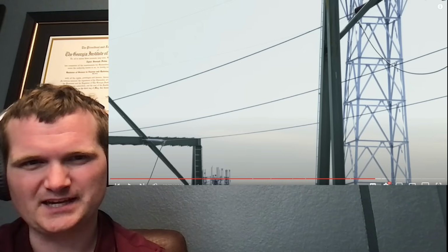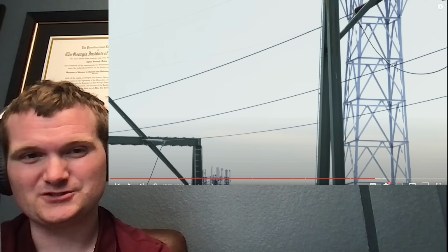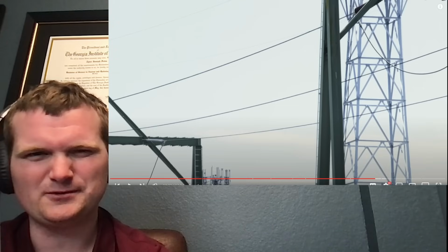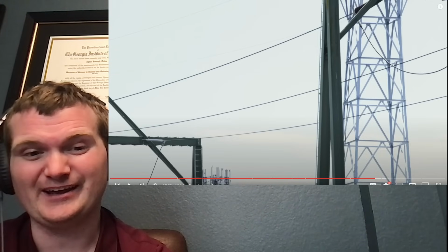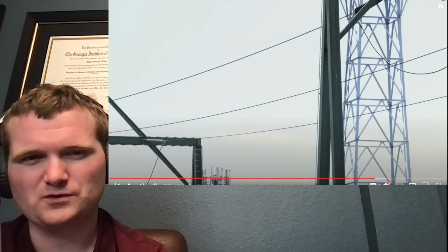Basically any sort of generator or transformer that's on the grid. A few years ago in Texas, there was a freeze, where a lot of power plants, especially wind turbines, were shut down. And there were moments in time where the grid was on the order of 5 minutes out from having to shut down and do a black start, which is starting from completely de-energized. And that would take a while. So during that freeze event, whereas a lot of people were without power for a few days, maybe a week, I don't exactly remember, this could have brought it up to several weeks to months, because it's a very coordinated and concentrated effort. It has to be done in sync in some cases, hence, to maintain that frequency. It's a very controlled startup.